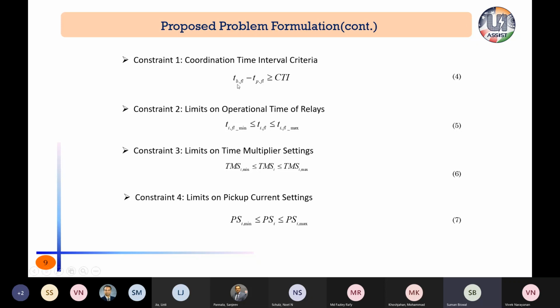So here T_B, the backup relay time for a fault at the same location sensed by the primary relay, minus the primary relay time, must be greater than or equal to the CTI. This coordination interval criterion must be satisfied. The second constraint is the operating time of the relays. The operating time of a primary relay must be assigned some timing, and we have assigned 100 milliseconds as per the standard value. That means it should take a minimum of 100 milliseconds to operate. For example, if the primary relay takes 0.1 second to operate, then the backup relay will operate at 0.4 seconds. Here we have taken 0.3 seconds as the coordination time interval criterion.